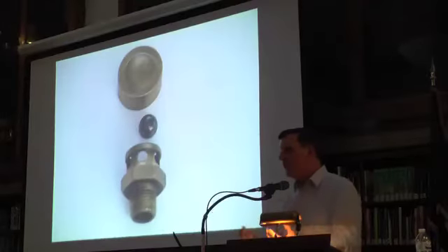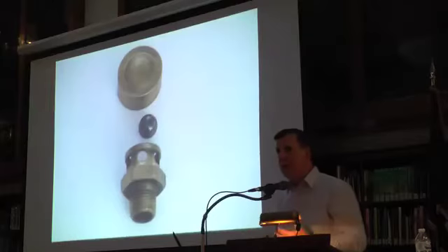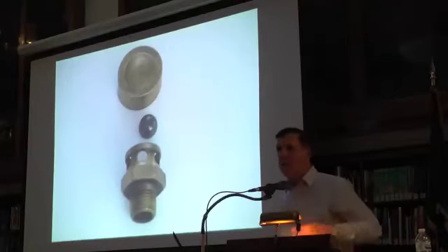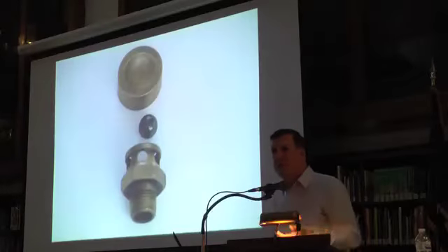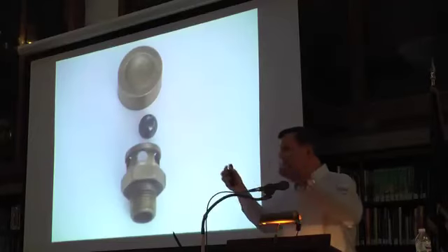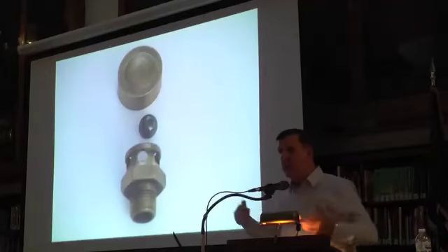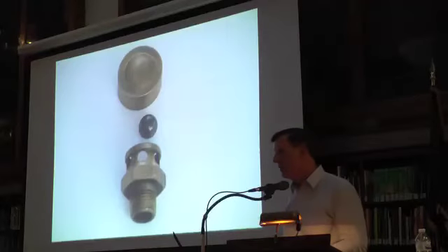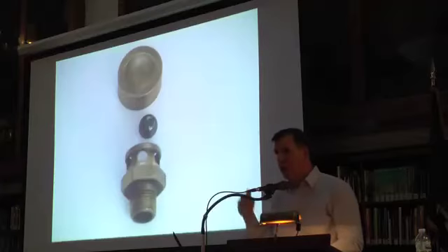The whole system goes into a deep vacuum. And in a deep vacuum, in the days when they were burning coal, you could boil water at temperatures as low as 160 degrees, and that's why they called it vapor heating. Because this steam would just waft off at an amazing velocity. Steam in a vacuum travels way faster than steam at 100 psi. The lower you have the pressure, the faster the steam will go.